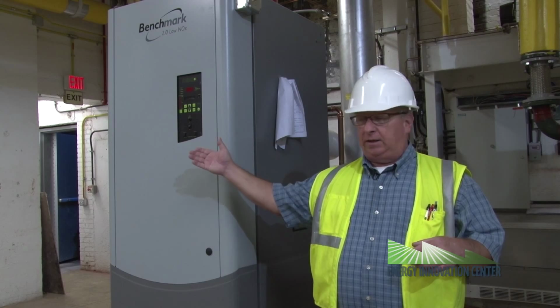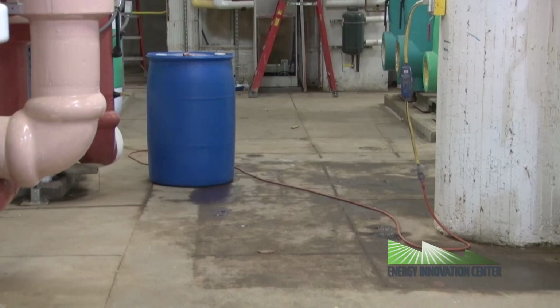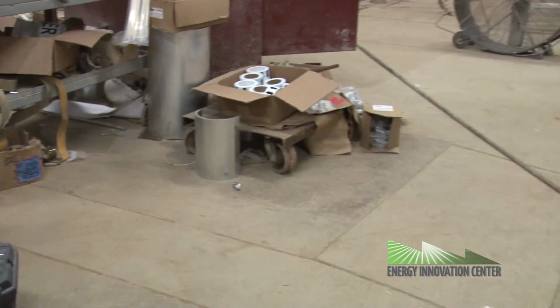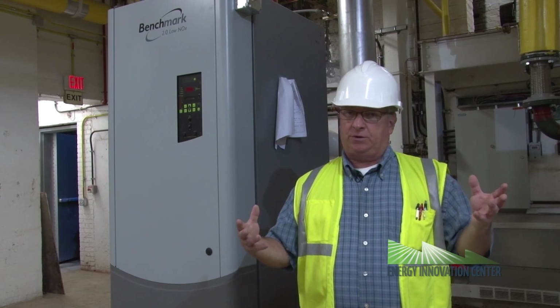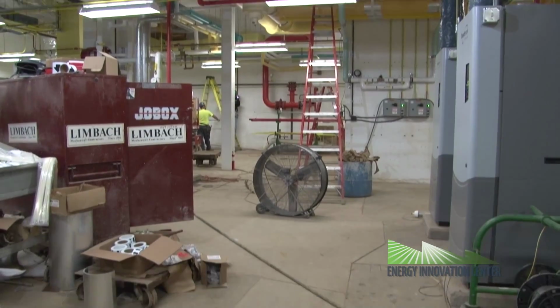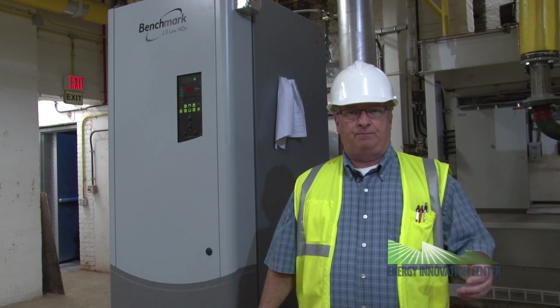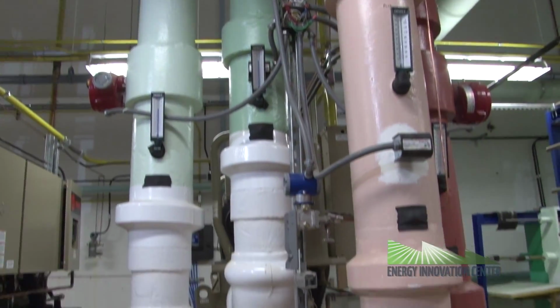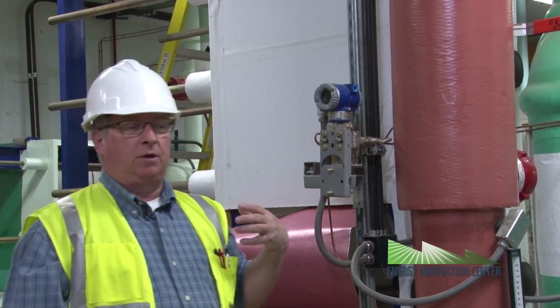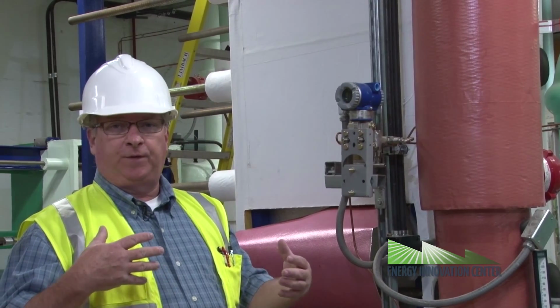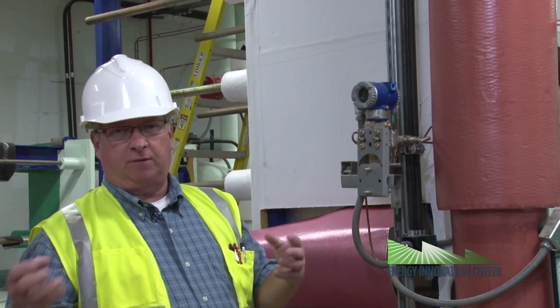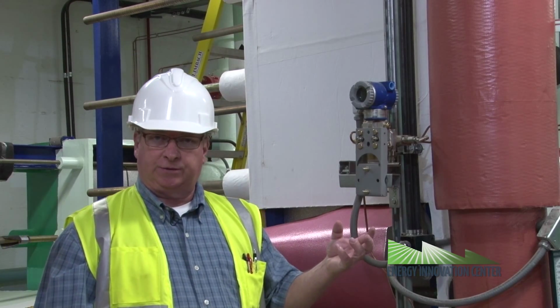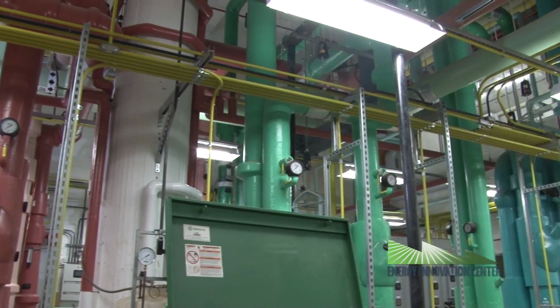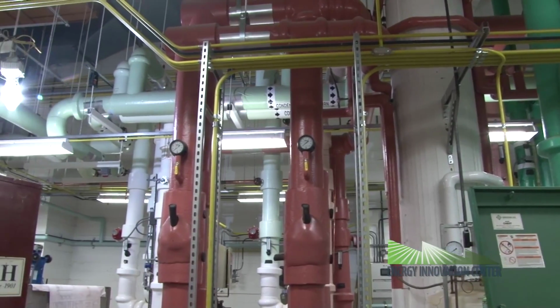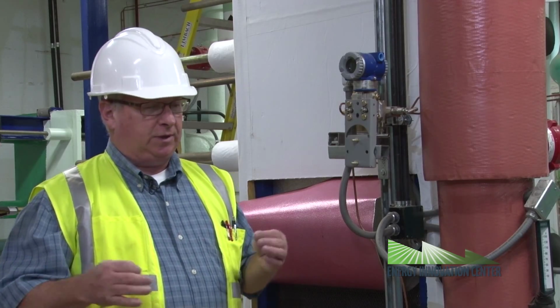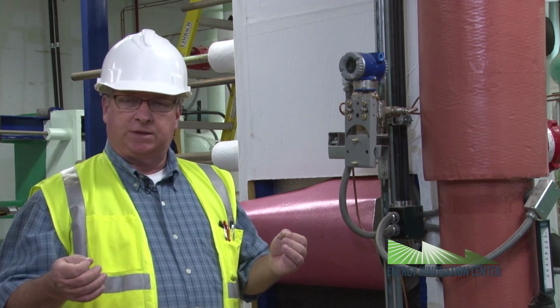As I mentioned before, in the other areas we have a wide open space, and we have large walkways because we're expecting large tours of students to come through. And so if we have a group of students, they'll be able to mingle around the equipment and see exactly how that equipment operates, how it's installed, and the reasons each device is in its place. One of the items we've specified is a significant amount of metering so that we can do our load calculations. The calculations of loads are based off BTUs. So if we can take our flow and our temperature differential, we can automatically calculate what our load is. And these load calculations are being fed back to our building automation system. Here we're going to the edge. We're using every capable operation of these systems we have in the building.